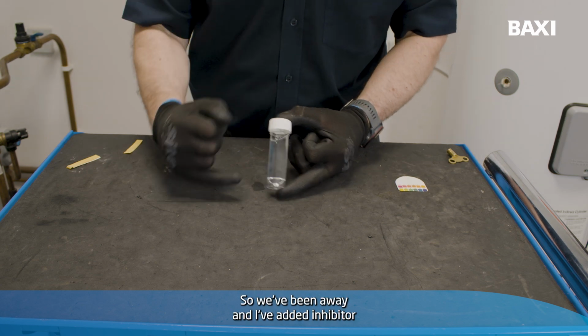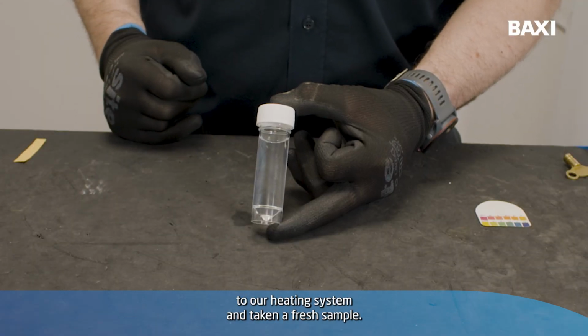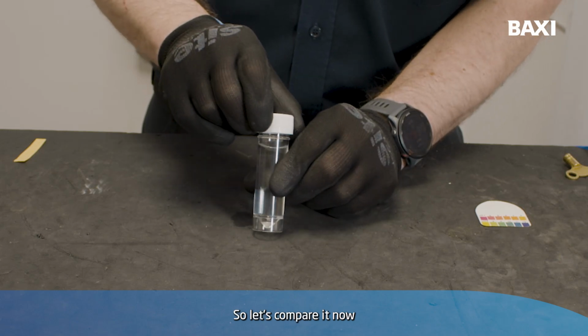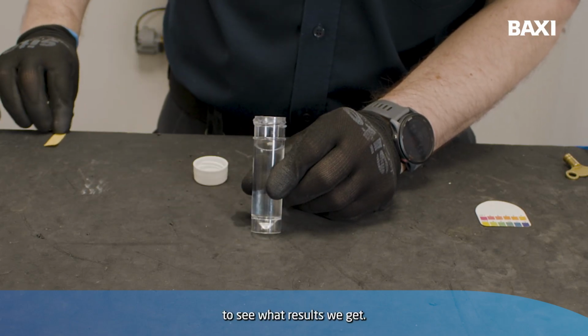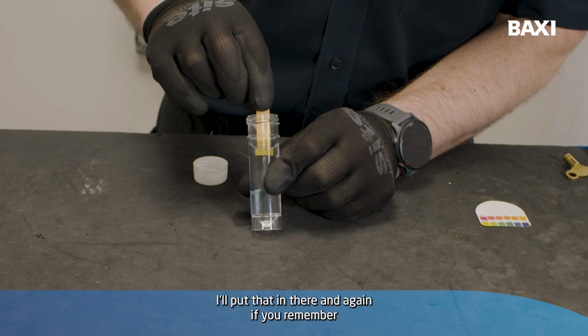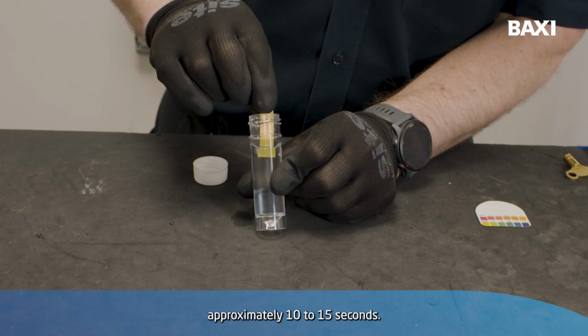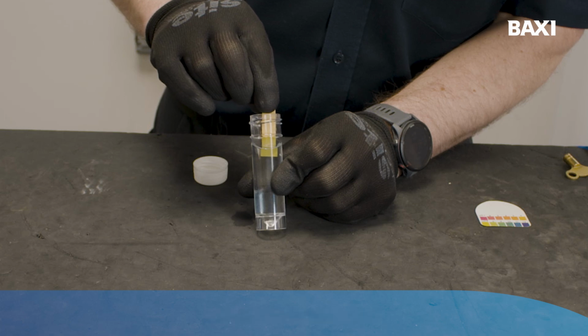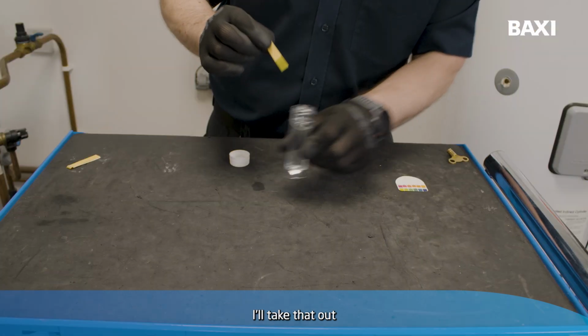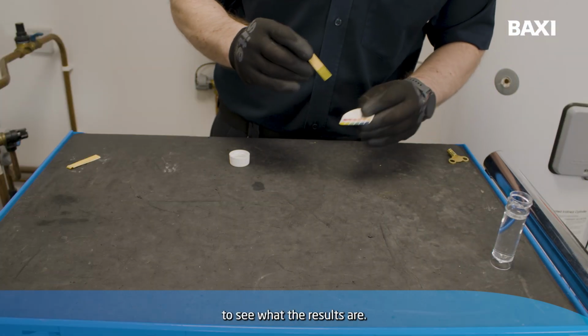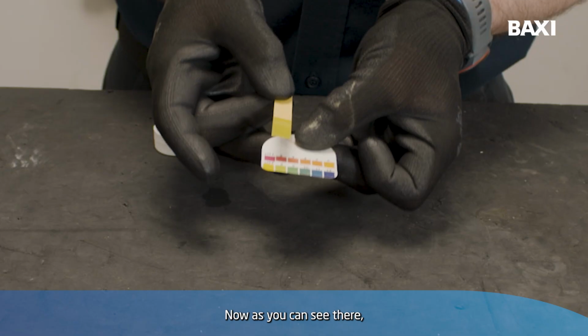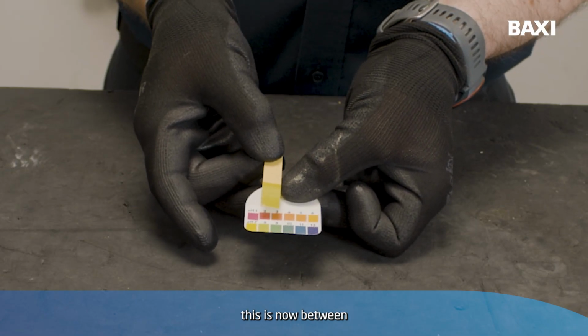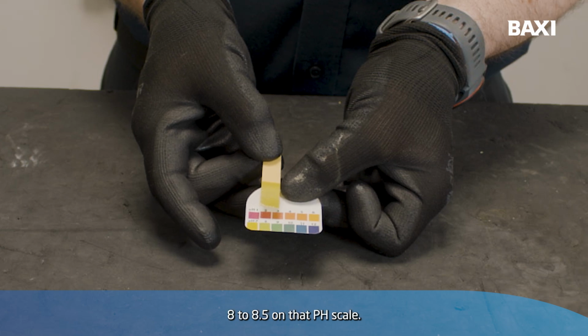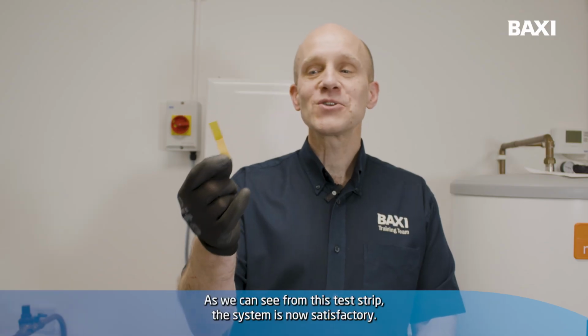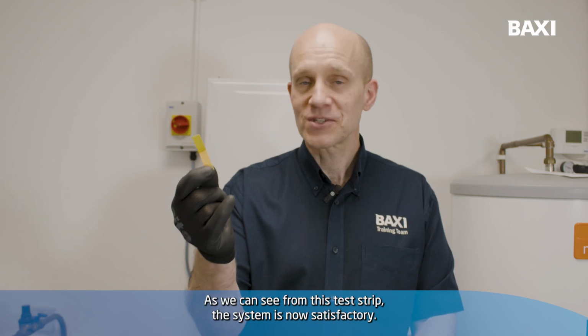Okay, so we've been away and I've added inhibitor to our heating system and taken a fresh sample. So let's compare it now to see what results we get. I'll put that in there. And again, if you remember, approximately 10 to 15 seconds. I'll take that out and we'll compare it to see what the results are. Now, as you can see there, this is now between 8 to 8.5 on that pH scale. As we can see from this test strip, this system is now satisfactory.